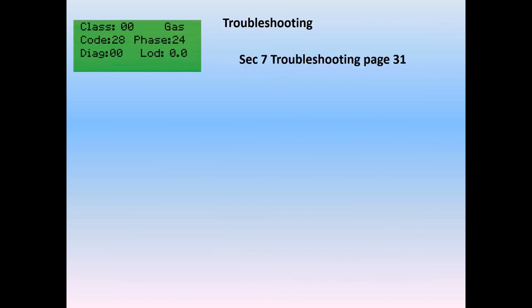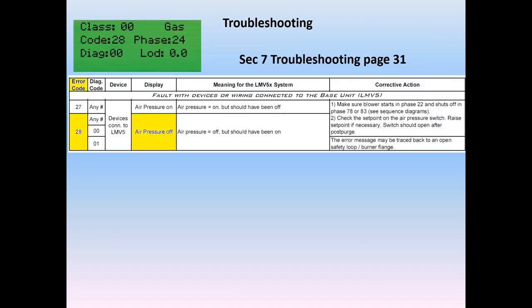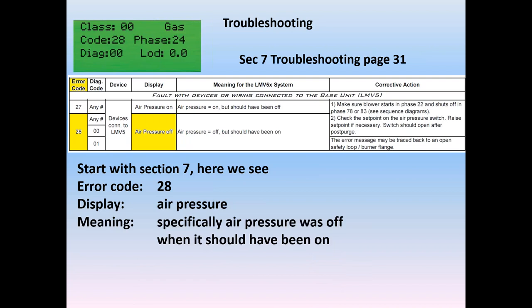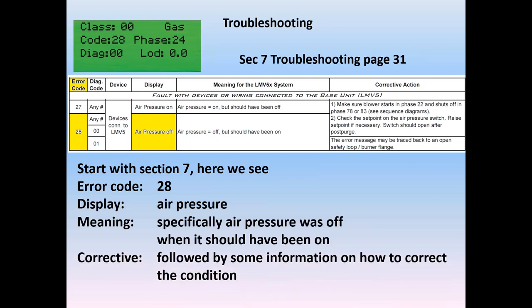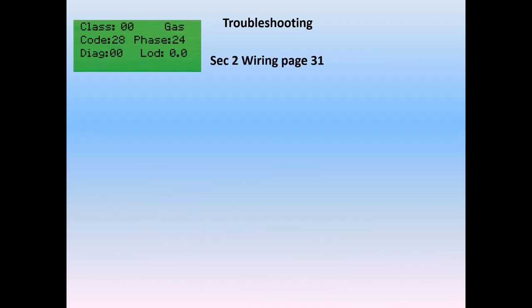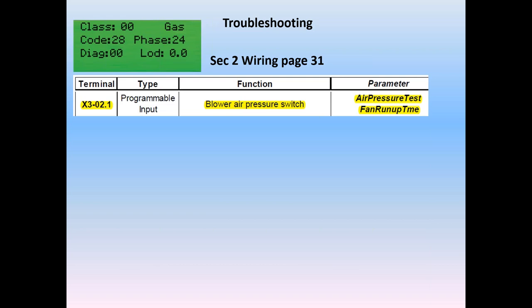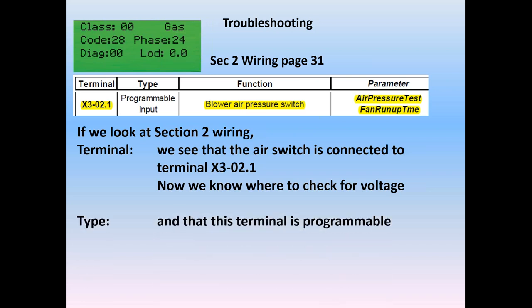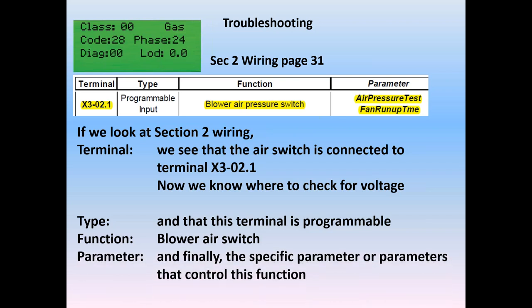Let's go into some troubleshooting. We'll take that exact fault — we'll start with section 7, troubleshooting. First thing we do is look up the code; in this case, code 28. The next column tells us that this is an air pressure fault, meaning specifically that the air pressure was off when it should have been on. Then we get a corrective action followed by some information on how to correct the condition. Now we can proceed to section 2 on the wiring. At page 31, we see that the air pressure is controlled by terminal X3-02.1. Now we know exactly where to meter to check for voltage to see if the air pressure switch is making or not. We also know that the terminal is programmable; the function will be air pressure switch.